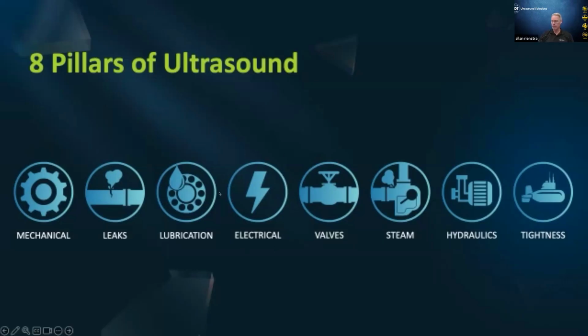Finally, the application pillar of electrical, well, that's what this presentation is really about. This is the breakdown of dielectric material insulating the transfer of electricity through systems. As that breaks down, it produces distinct characteristic noises, which we can hear very clearly in the 40 kilohertz range. Valves: again, turbulent flow across the valve head tells us whether the valve is open, closed, cavitating, or flashing. Same with steam in a steam trap. If steam is leaking to the atmosphere or the steam trap itself isn't working, we can detect friction, impacting, and turbulence to determine the condition of a steam trap. Hydraulic systems are mostly mechanical, but also some flow, so flow through pipes and turbulence. And then finally, tightness testing. Those make up the 8 pillars of ultrasound, the applications of ultrasound.